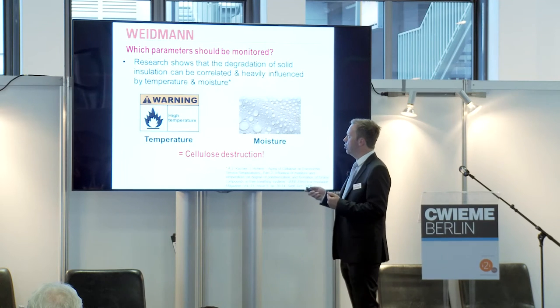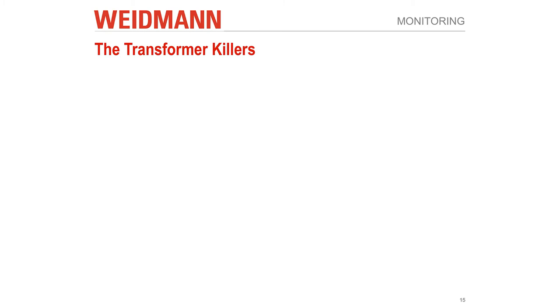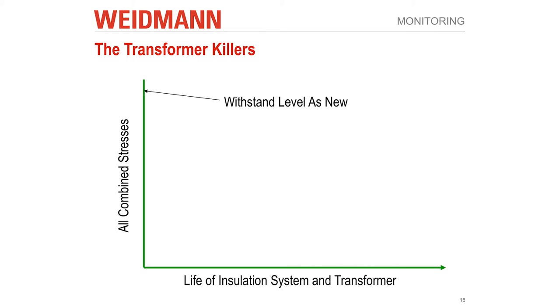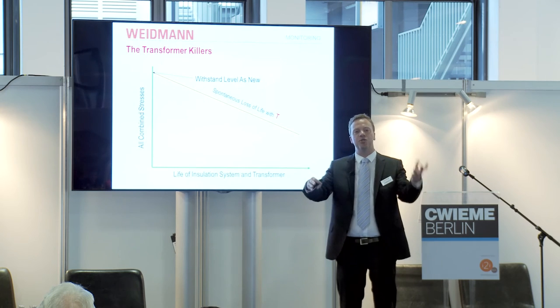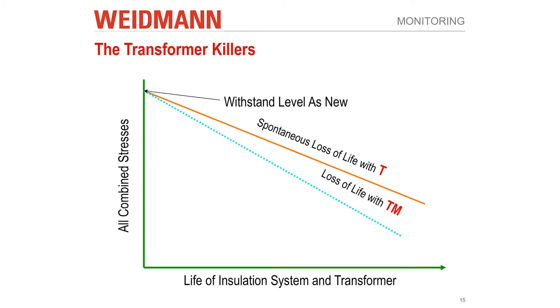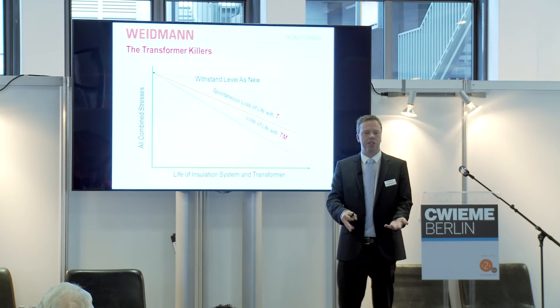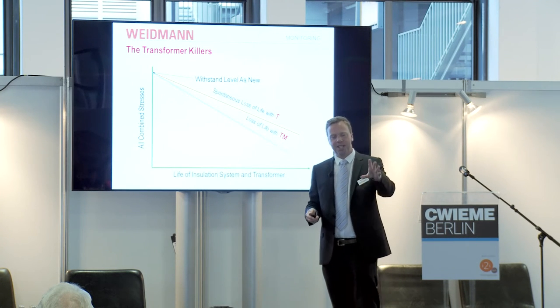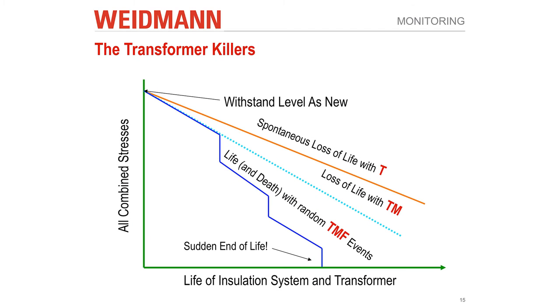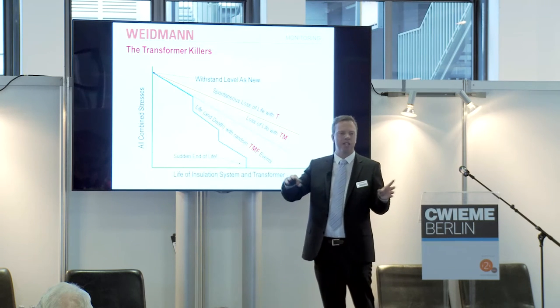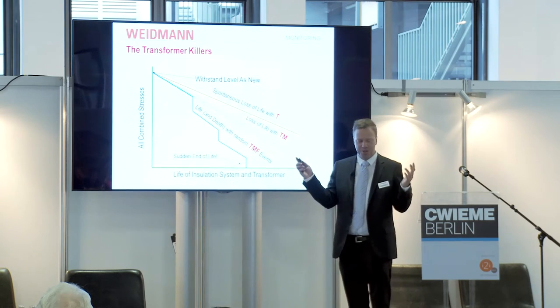Moving on, even more dramatically, we're calling these the transformer killers. What are they? Your withstand level with a new transformer is great because it's high. But if you introduce high temperature, the age of the insulation in the transformer declines. If you introduce moisture, along with temperature, this increases the rate of decline of the insulation. Now I'll add an extra one not on the last slide: force, meaning the actual clamping force of the transformer. I'll explain later what that means and why it's relevant. So these are the transformer killers.